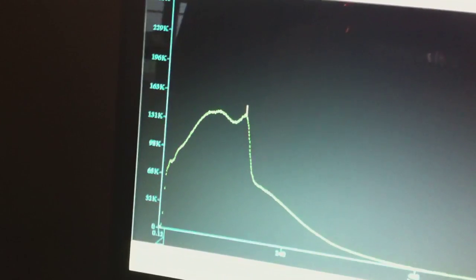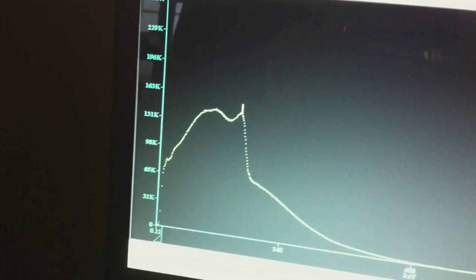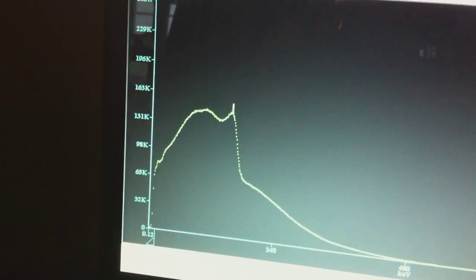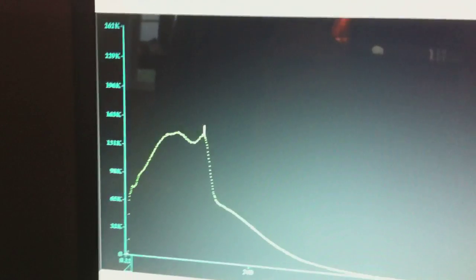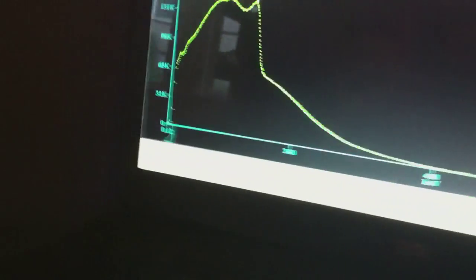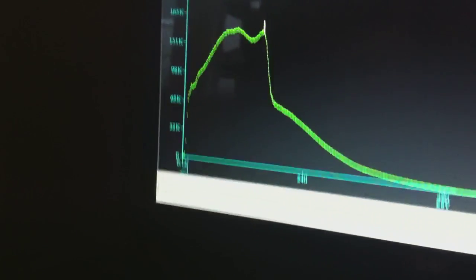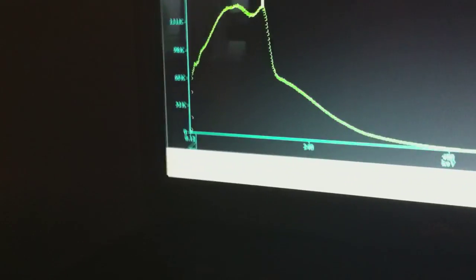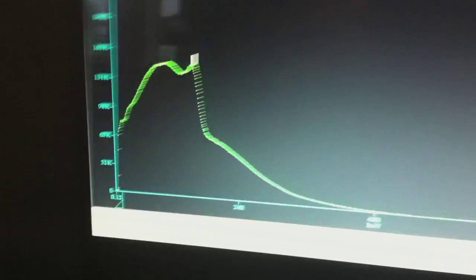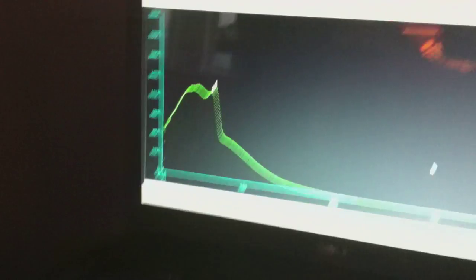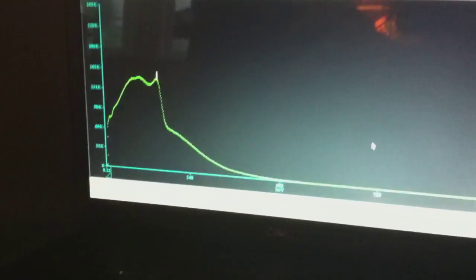And as you can see, the activity light is solid because it is flashing too fast for the eye to perceive a difference. And as you can see right here, there is a spectrum forming from what is probably technetium-99. The calibration is slightly off. As you can see, we have 146,000 counts, 147,000 counts, 148,000 counts, and so on, and just that channel alone. Amazing!